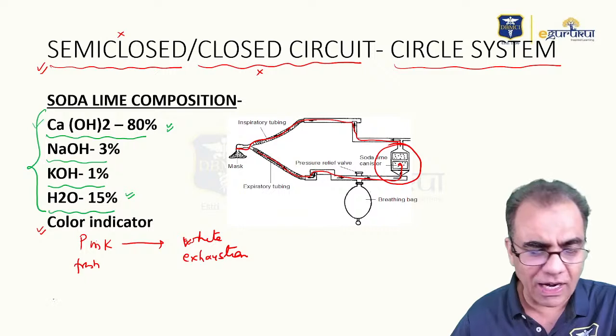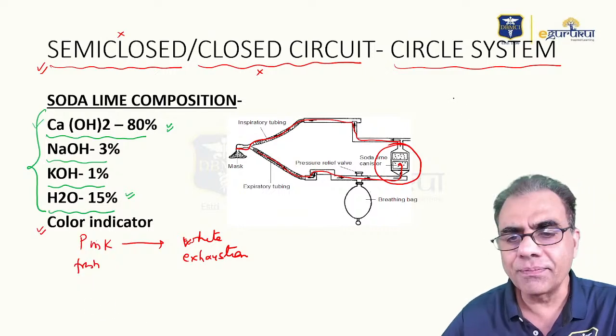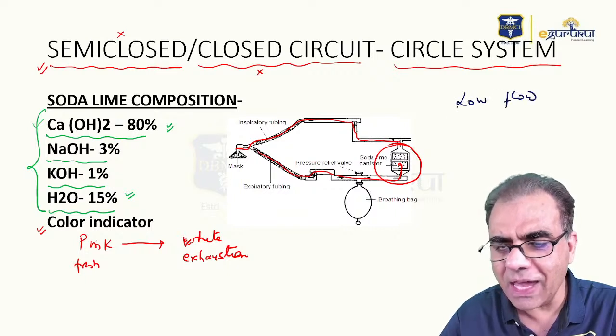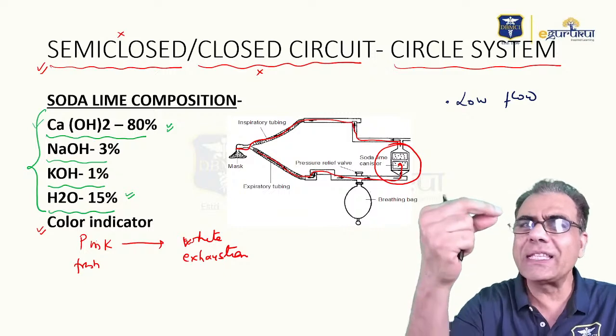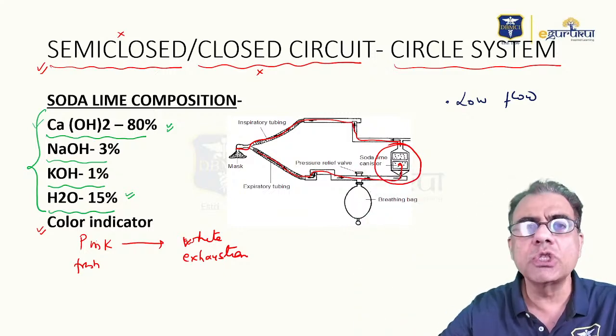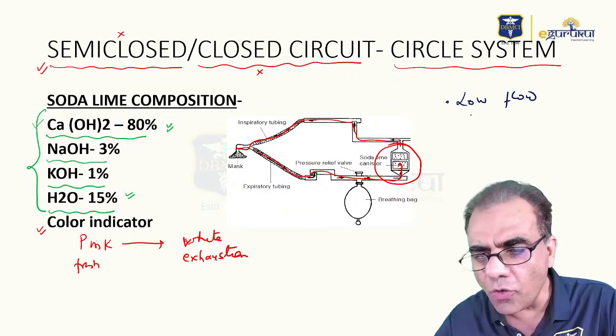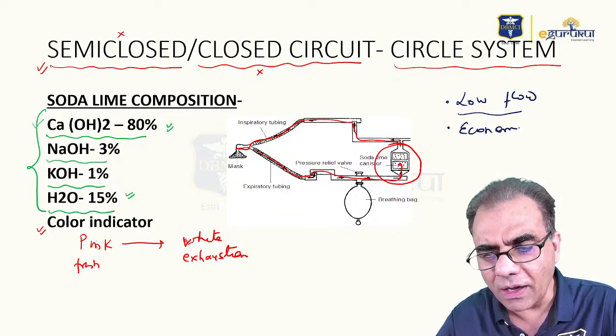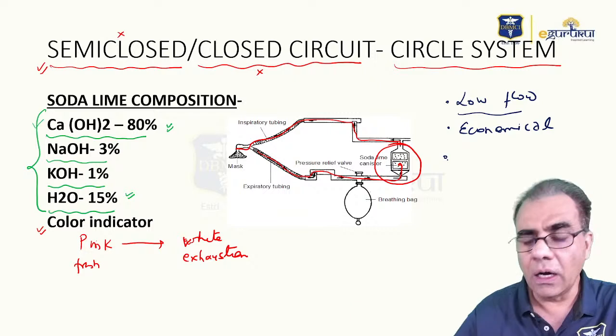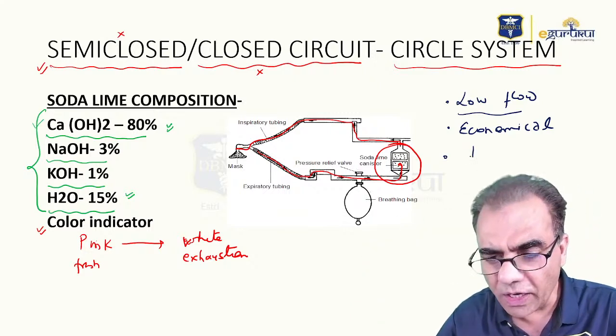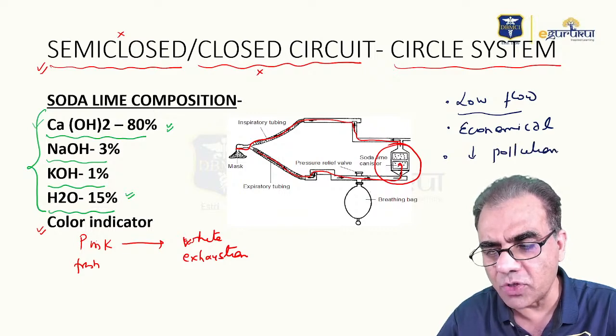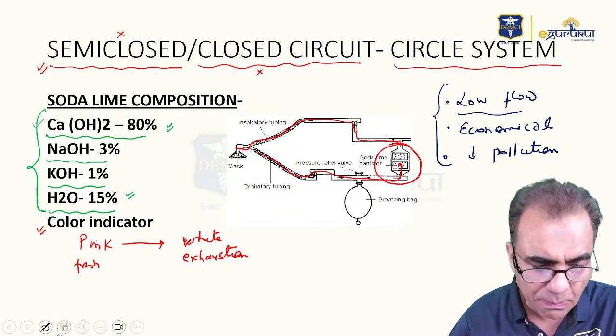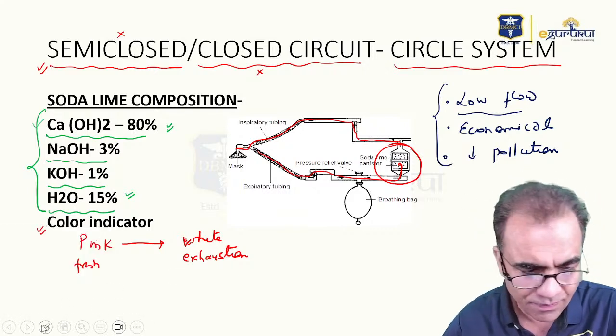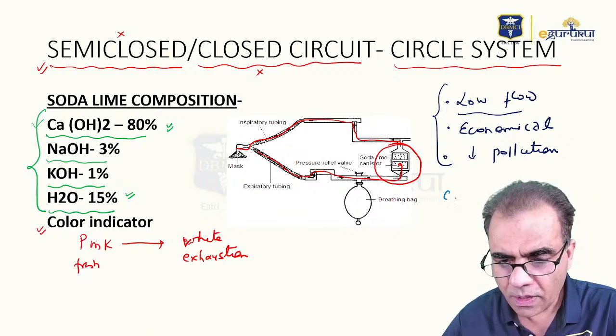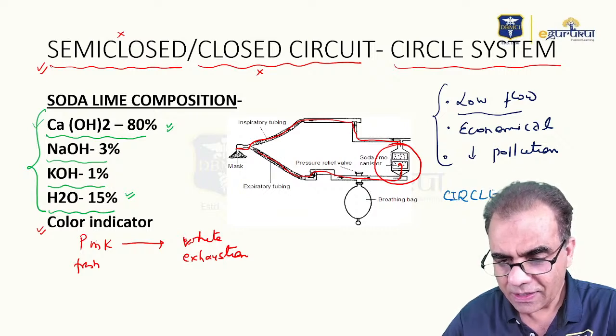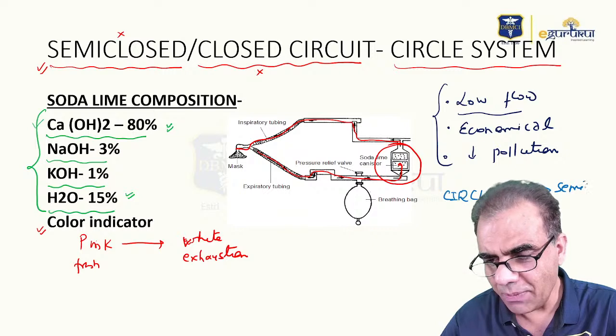So what is the major advantage of this circle system? That it uses low flows. See, the same gases are in circulation, so only the few gases lost due to leakage or the oxygen consumed by the body need to be replaced. So very low flow, and that makes anesthesia very economical, and less gas is vented out into the atmosphere. So there is very little theater as well as atmospheric pollution. Because of these reasons, simply you can say that circle system is preferred over semi-open.